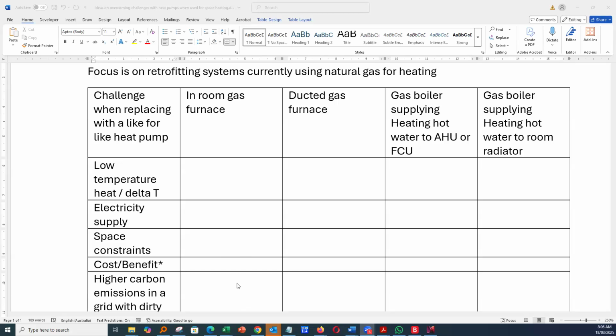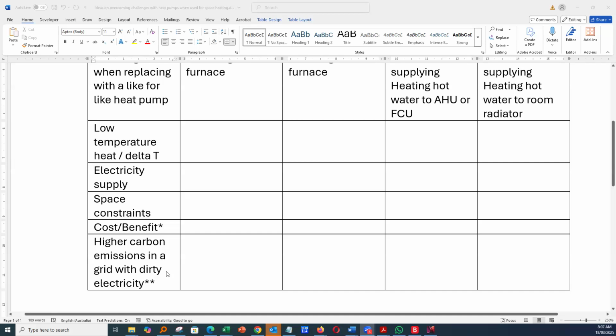So a COP, let's say a system with a higher COP, like a split system where the temperature of the heat is relatively low, will have a higher COP than a system where you're using a two-stage heat pump to get your water temperature up to 75 degrees Celsius. So then the COP will be lower, which means you need more electricity to produce the same amount of heat. Therefore the cost benefit drops. So again, particularly with this gas boiler situation, that becomes more of a challenge.